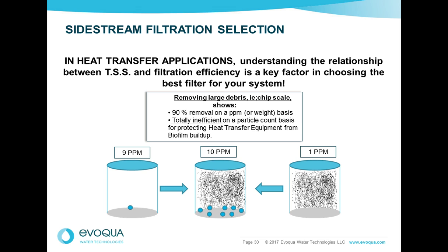When dealing with heat transfer equipment, understanding the relationship of total suspended solids and a filter's removal capability is key. As Bob also said, the smaller particulates tend to foul heat exchangers first, not the big ones. So if you only look at particle volumes and ignore the counts, you may miss that small particulate.